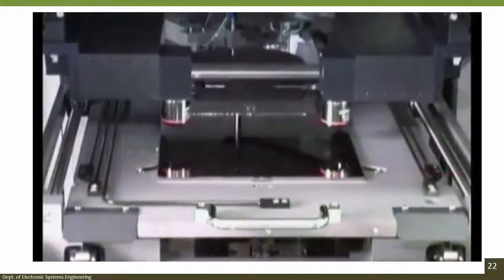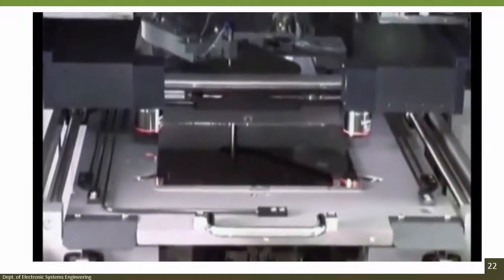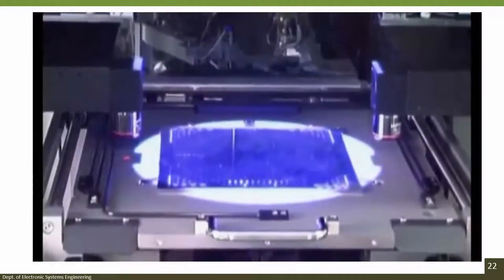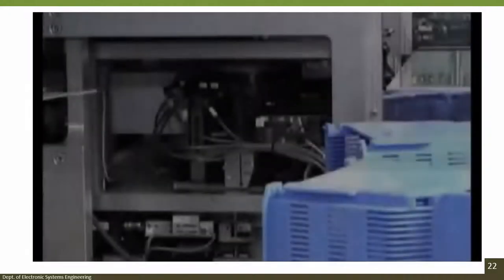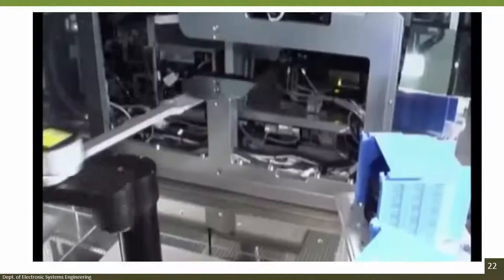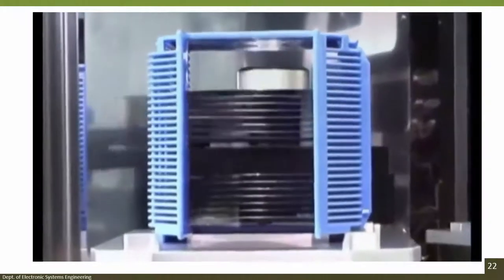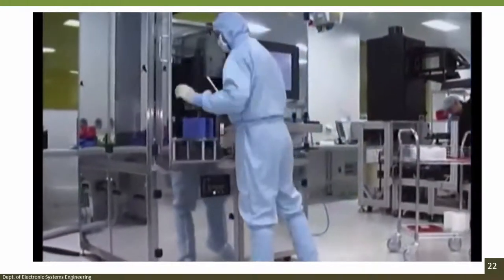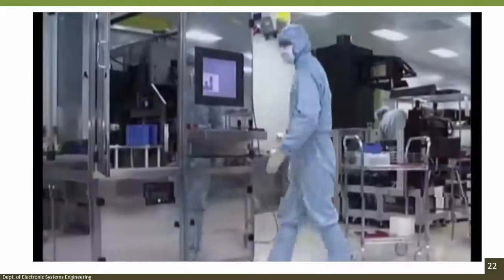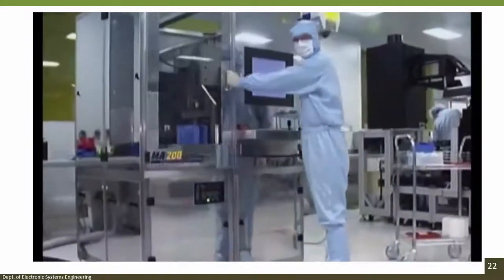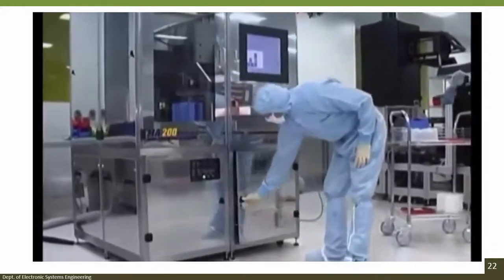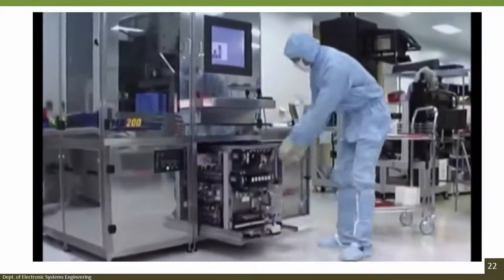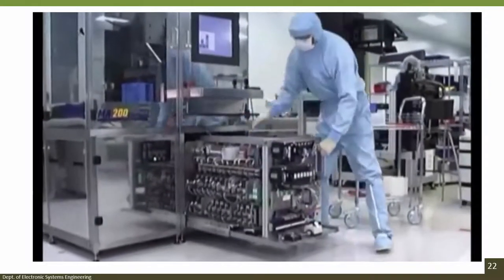In thin resists, it achieves a resolution of 3 microns in proximity mode and a submicron resolution in contact printing. A microscope for bottom side alignment is optionally available. It can process substrates with thicknesses of up to 4 millimeters. The MA200 Compact is a master when it comes to detail. Our idea while designing it was to create a device that is both user and maintenance friendly in order to further reduce your operational costs.